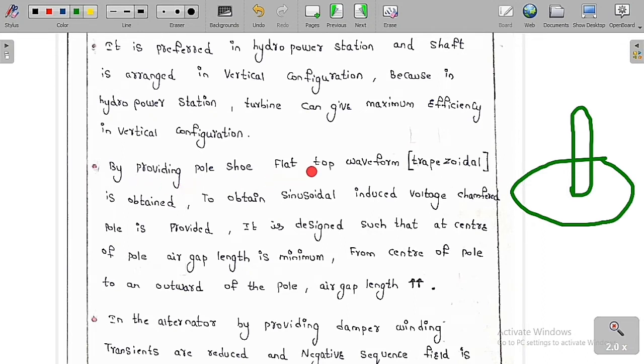By providing the pole shoe, a flat topped waveform, which is called trapezoidal, is obtained. To obtain sinusoidal induced voltage, a chamfered pole is provided. It is designed such that at the center of the pole, the air gap length is minimum, and from the center of the pole outward, the air gap length increases. So by providing a pole shoe, a flat top trapezoidal waveform is obtained. If you provide a pole shoe for the poles, we get a trapezoidal waveform induced in the voltages. If you want to obtain the sinusoidal induced voltage, a chamfered pole is provided. If you provide a pole shoe for a pole, the waveform we get is a trapezoidal, or flat top, waveform in the induced voltage in the coils.